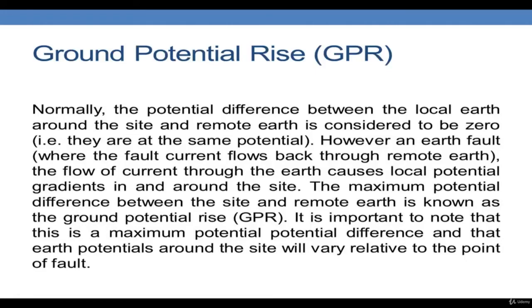And next is the ground potential rise. The potential between the local earth and the site is considered to be zero at normal condition. However, when a fault occurs, the flow of current to the earth causes a potential gradient in and around the site. The maximum potential difference between the site and the earth is known as the ground potential rise, or the GPR. It is important to note that this is a maximum potential difference, and that earth potential around the site will vary relative to this point. So during the period of fault, the potential in the site will increase compared to that of the local earth. That potential is called the ground potential rise.